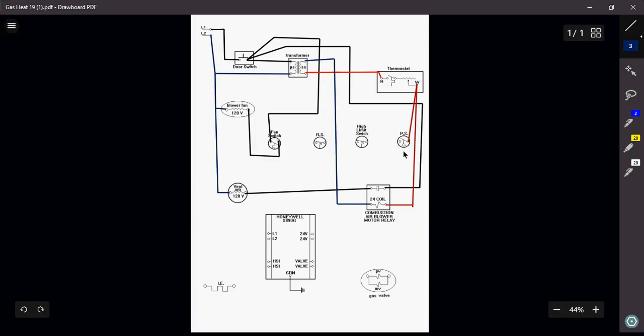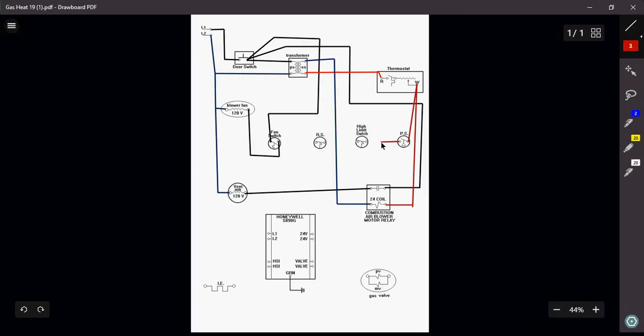So I'm going to take that pressure switch and I'm just going to simply wire it in series with my high limit switch and my rollout switch. Okay? Like so. I'm going to go just like that. One right after another. That's my safeties right there. That's my safety circuit. This guy right here is so important to the operation and the safety of my furnace.